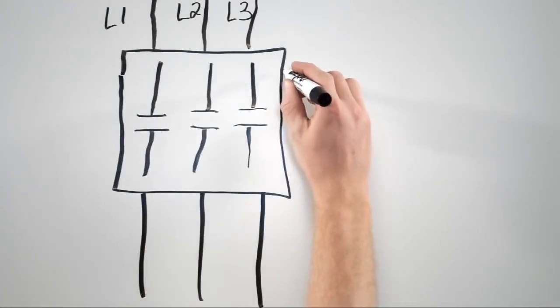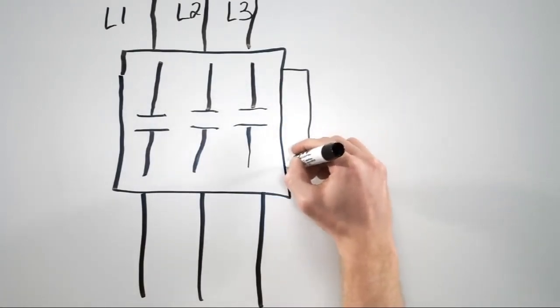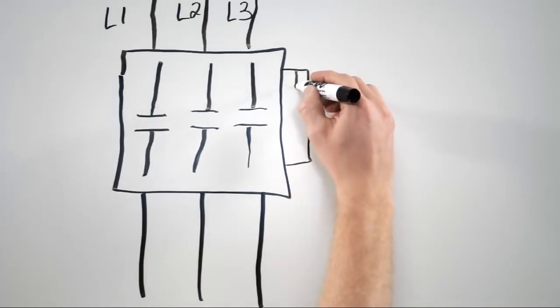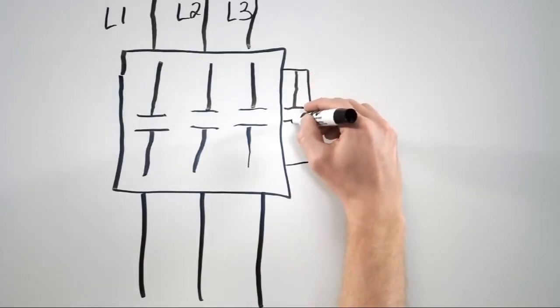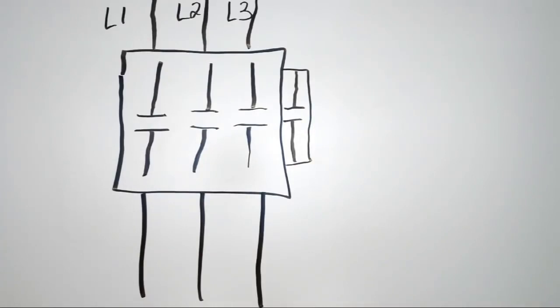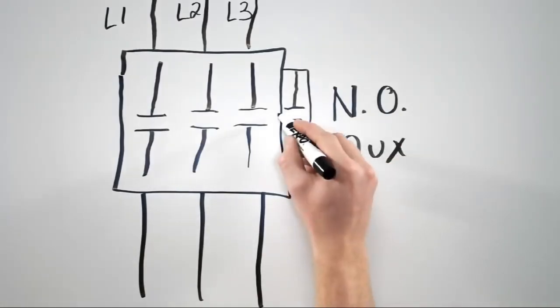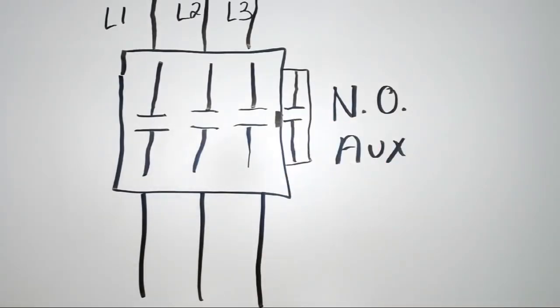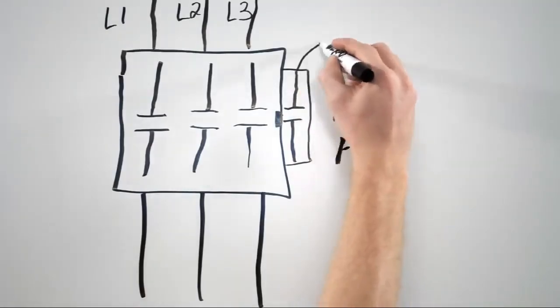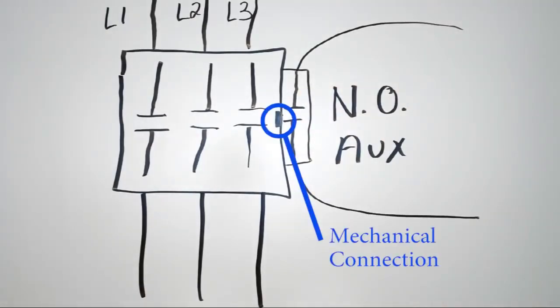Well, there is a very common accessory that gets added to contactors called an auxiliary contact. Often it's mounted to the side of the contactor, and inside the auxiliary contact module, we have an electrical contact that can be normally open or normally closed. I've drawn a normally open auxiliary. If you grab a normally open auxiliary off of the shelf, it will not pass electricity through it unless it gets changed by an outside force. When it gets attached to the side of a contactor, there is a mechanical connection between the auxiliary contact and the moving parts inside the contactor.